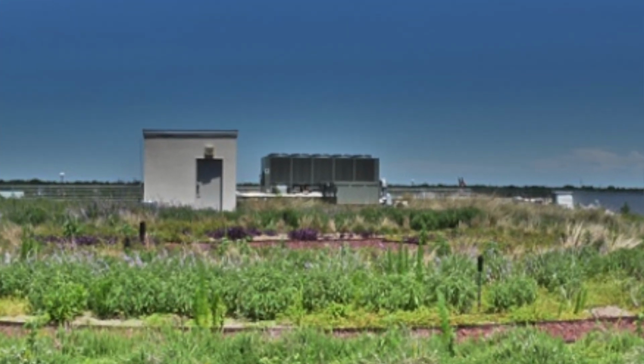It's a dual circuit machine with a 60-ton and an 80-ton compressor. Since they are dual circuit standalone with incremental capacity, we've found over the years that during off-demand periods, using the 30% incremental capacity on the 60-ton circuit, we're able to cool the building with approximately 18 tons.